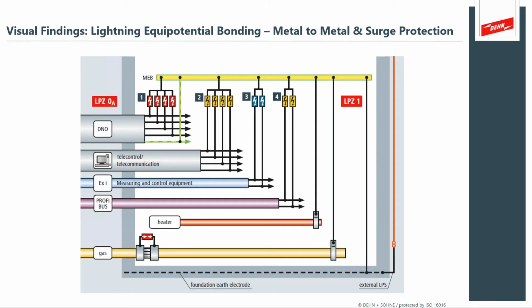Visual findings: lightning equipotential bonding, metal to metal, and surge protection. So wherever possible, for instance, in copper water pipes or in black gas pipes, you're bonding the metal to metal. But what you find is that electrical surge protection is used to bond the equipotential voltage of conductors. So you can't bond it, but you can control the voltage. And that's what that SPD is intended to offer right here on that main AC power. You have your ground is bonded, your green-yellow ground, but the SPD provides a voltage control for what you cannot bond.